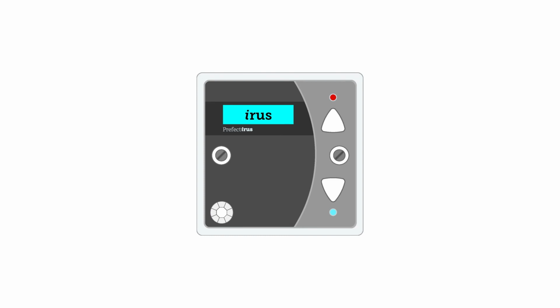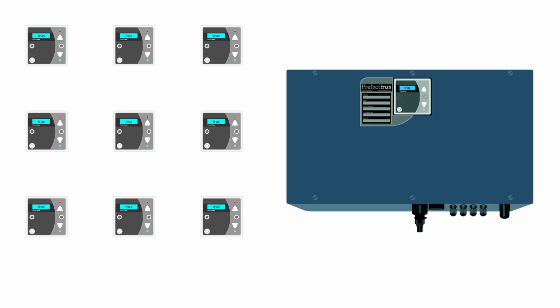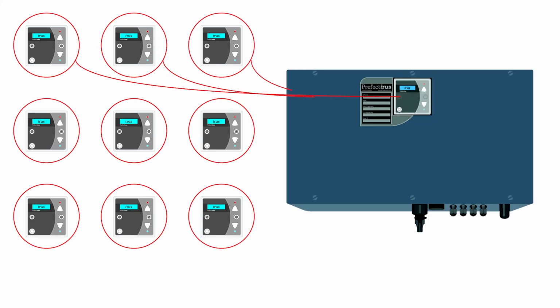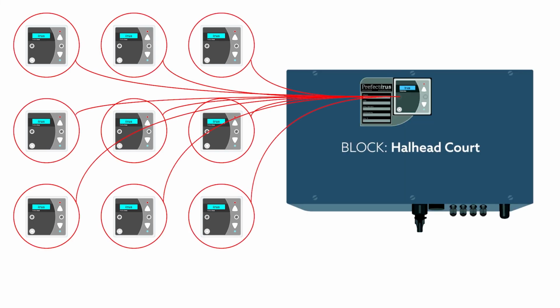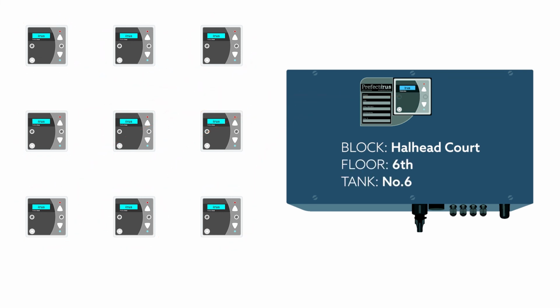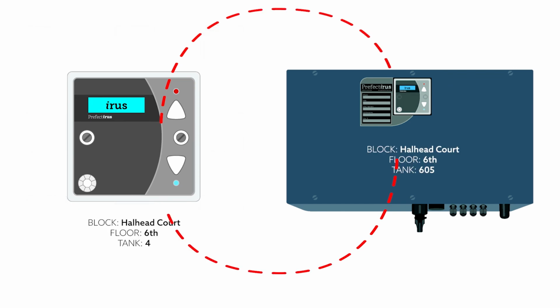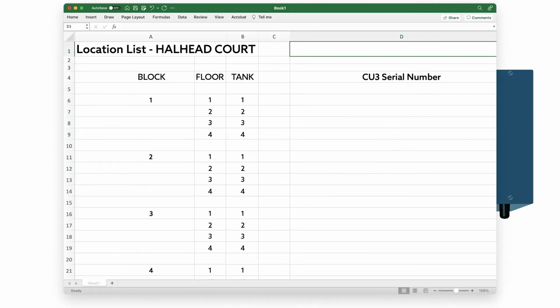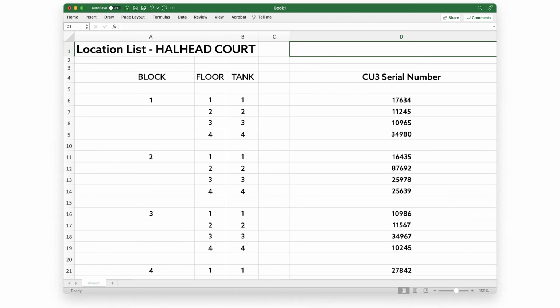When the control units have been installed, the master interface unit needs to identify each of their locations: the block, the floor, and the tank it is controlling. It is essential that this is done accurately, so we know that we are controlling the correct tank. A location list will have been drawn up prior to installation. What we need from you is the serial number of each control unit and which tank it is controlling.